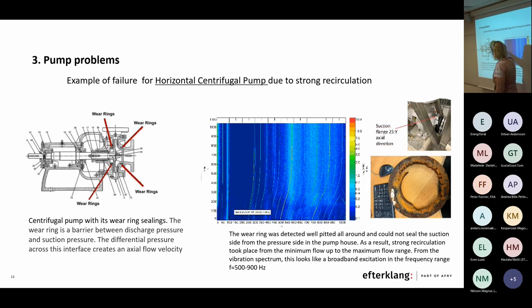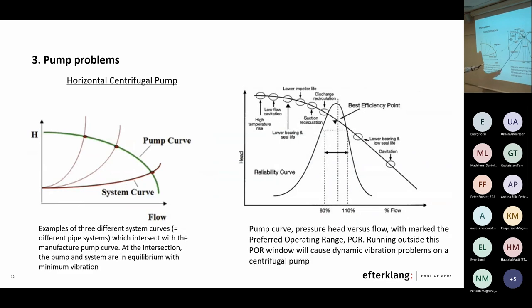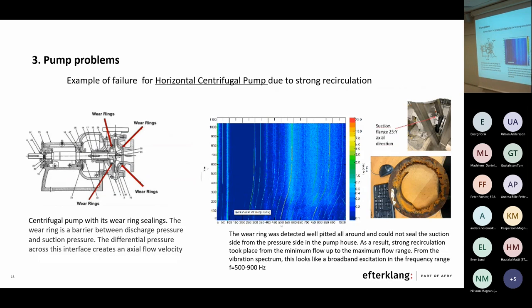And this has to do with the rotor inside here. It had been worked in a non-matched pump curve, system curve configuration. So it had worked. It has not worked in this position. It has been driving here all the time without verification. So it's wear and tear, but the water is pumping, so almost no one goes down here and looks at the pump. So then it looks like that.